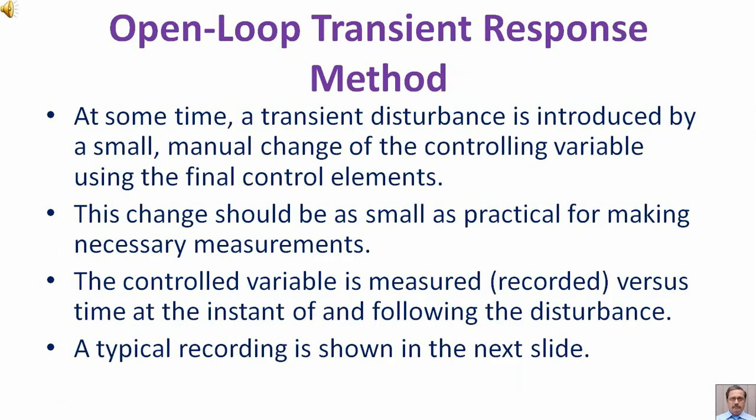Open Loop Transient Response Method. At some time a transient disturbance is introduced by a small manual change of the controlling variable using the final control element. This change should be as small as practical for making necessary measurements. The controlled variable is measured, recorded versus time at the instant of and following the disturbance. A typical recording is shown in the next slide.